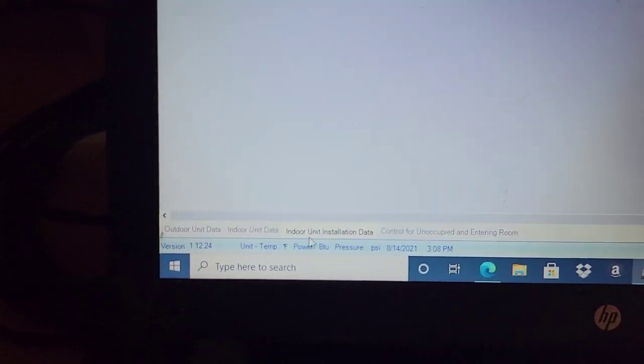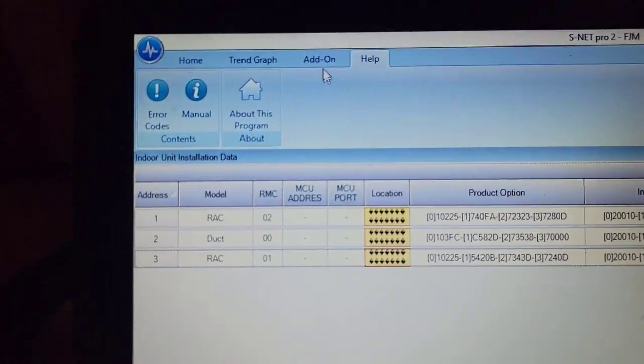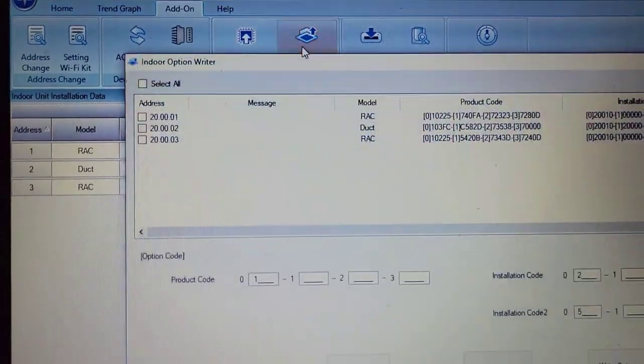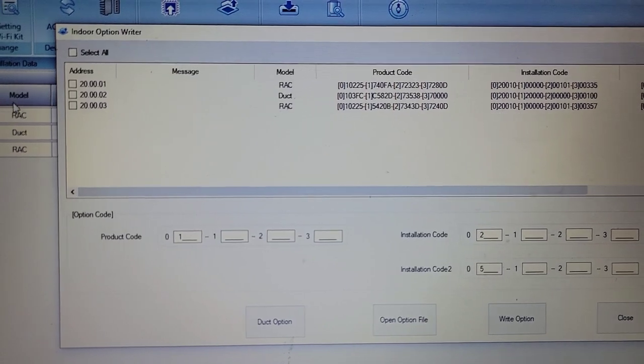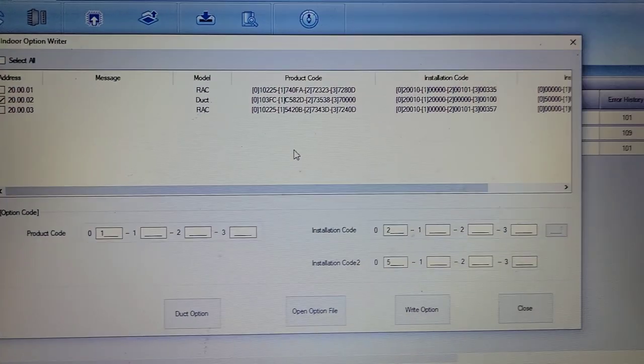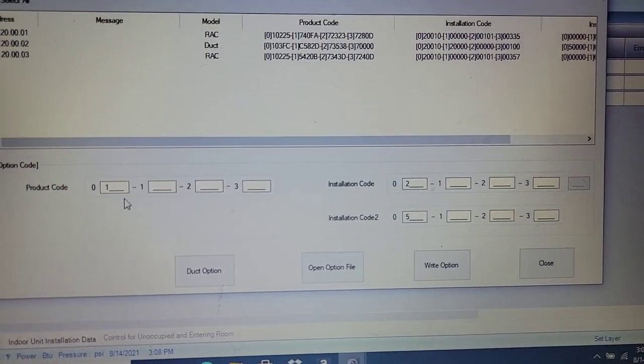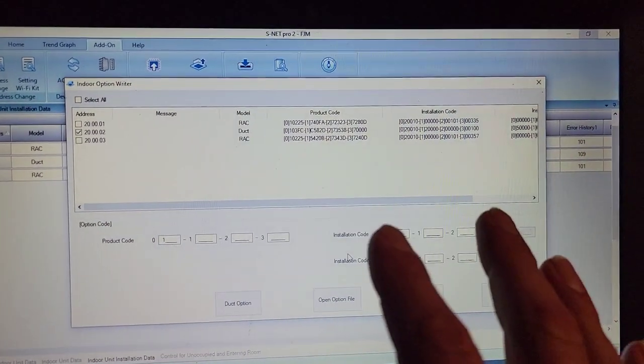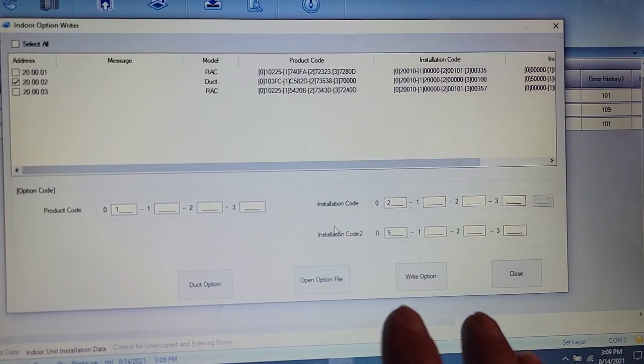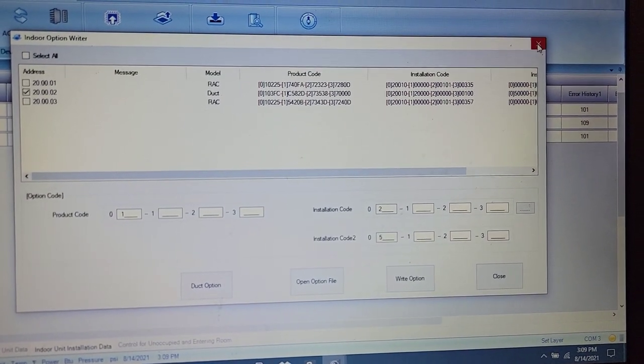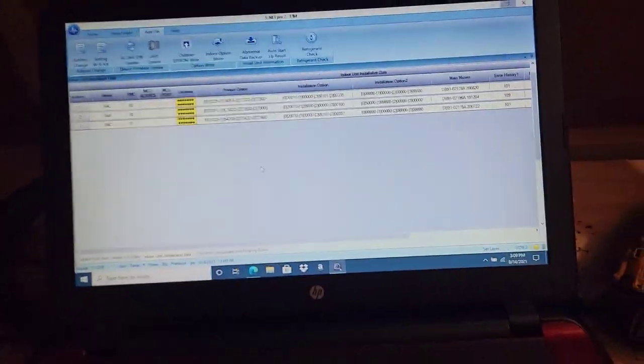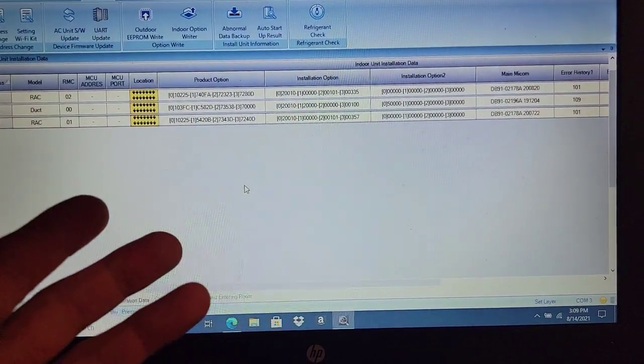Now, I'm going to show you where to adjust the options settings. Indoor unit installation option. We're going to go to add on. We're going to go to Indoor Option Writer. We're going to select the ducted unit right here, and we're going to be able to change the product code. If I wanted to adjust the fan speed, or if I wanted to change an option setting and make it to where I'm not using the drain pump, or I am using the drain pump, then I can do that very easily.